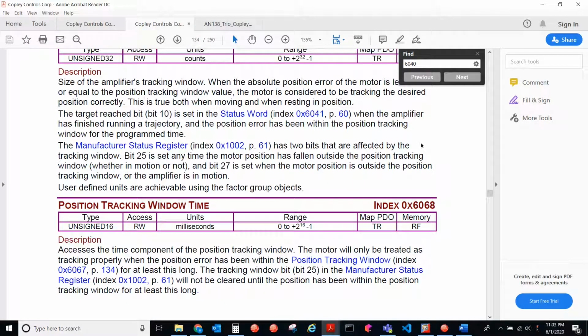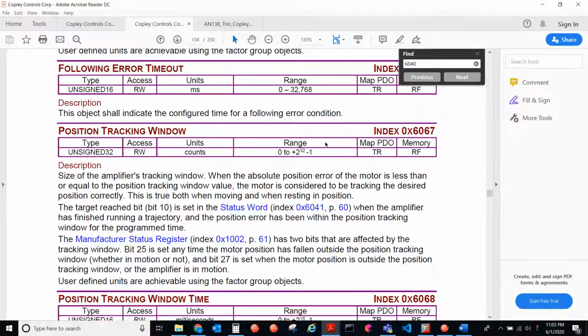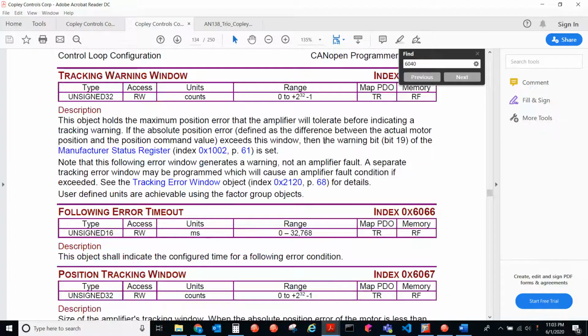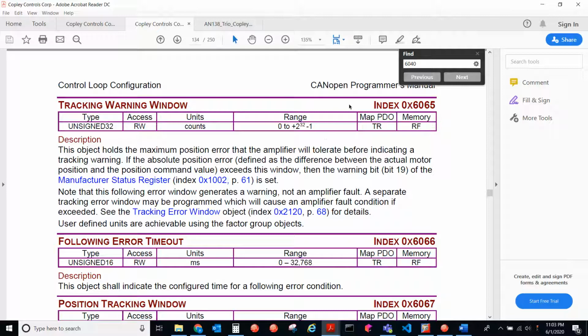So for axis A, this is correct, 6068. But for axis B, the index is actually going to be 6868. For axis C, 7068. So that's how adding 800 will work for multi-axis drives, that offset.